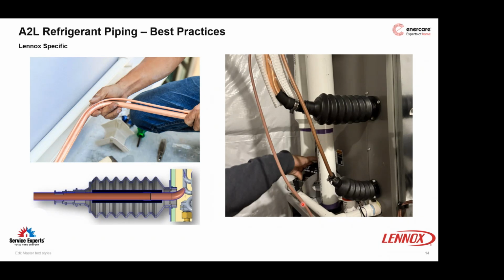If, God forbid, there's ever a leak at the joint, it will force it into this section of the coil. You can see how this open space here would push the refrigerant to where the sensor is located, and it'll activate those mitigation procedures from the RDS board. But not every installation has just one single joint at the sleeves. And as far as I know, Lennox is the only manufacturer that's actually utilizing this sleeve system. None of the other manufacturers are using it.